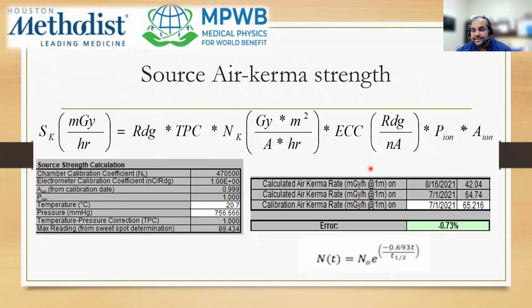So we basically use the air kerma strength from the day the source was made, in the source calibration document that you saw a couple of slides before. Then you calculate your air kerma strength on the day of the source exchange. You have your reading, your temperature pressure correction, your electrometer calibration factor, and your A-ion, P-ion factors, which are typically provided to you. And you do a back decay calculation based on today's air kerma strength.